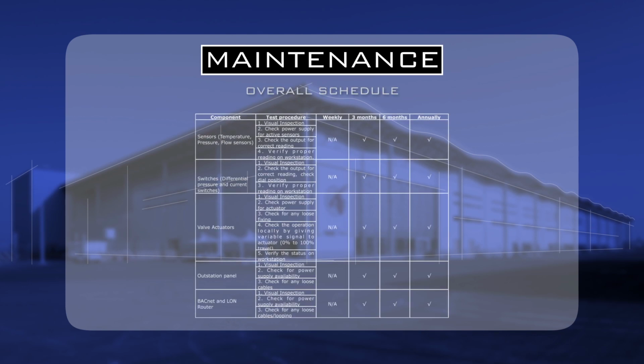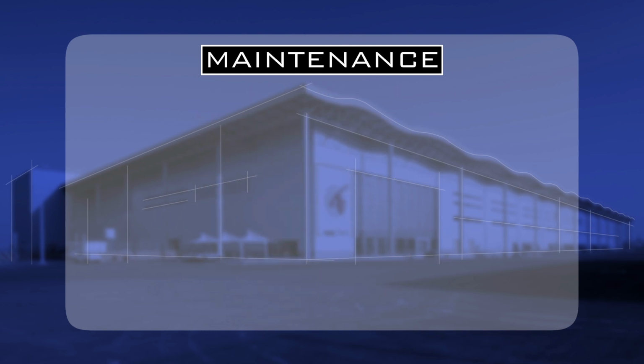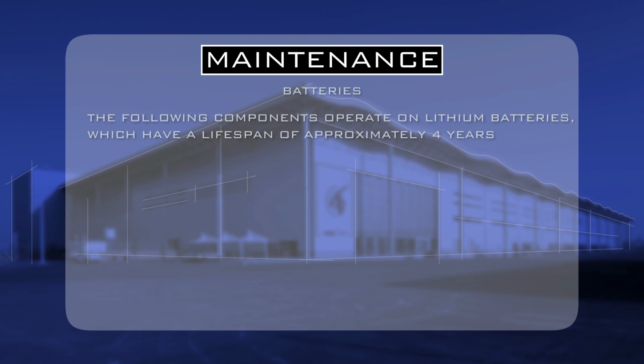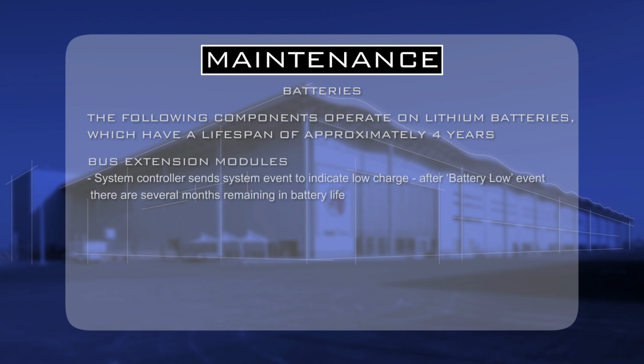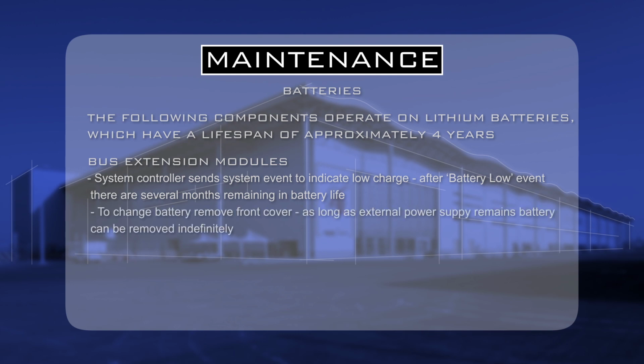The building management system should be regularly maintained. Some components operate on lithium batteries, which have a lifespan of approximately 4 years. These are bus extension modules. The system controller will send a system event to indicate low charge, though there will be several months of battery life following this. To change the battery, remove the front cover. As long as an external power supply remains, the battery can be removed indefinitely.